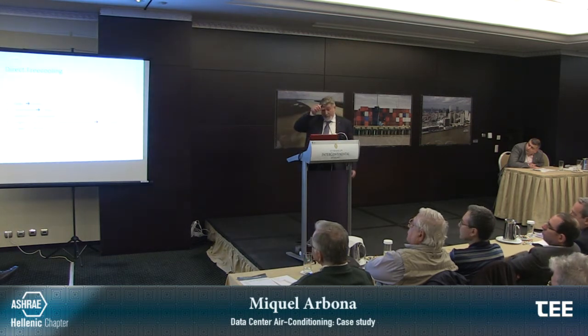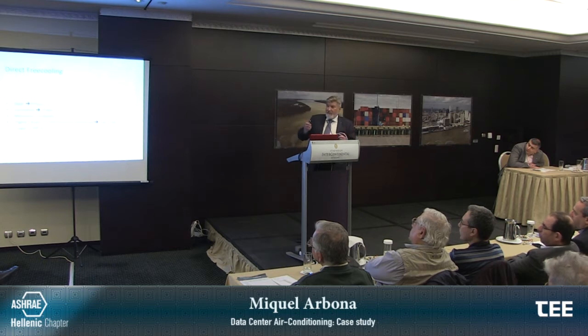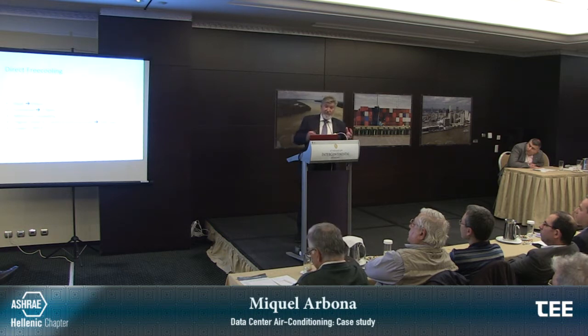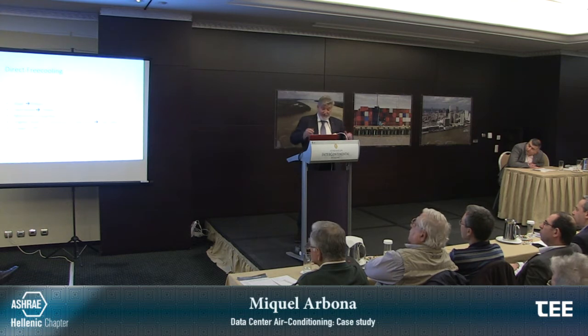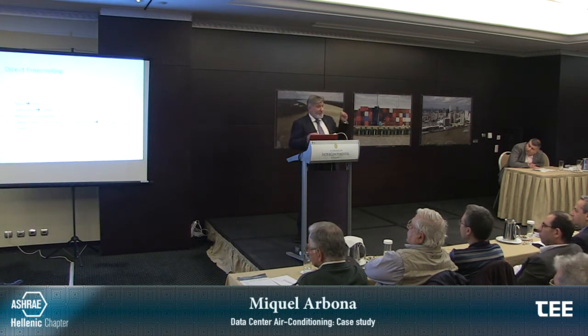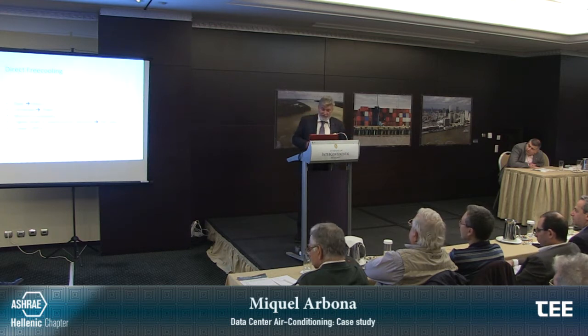But they have some problems. Sometimes the typical problem is dust. A lot of dust and pollution comes in, so you have to put a lot of filters in the direct system. Also the moisture; humidity is very difficult to keep at the right point. And you have a lot of people running around, because the sensors have to be very well calibrated. Otherwise, you have problems with the stability of the system. Yes, we have lower capex but higher opex.